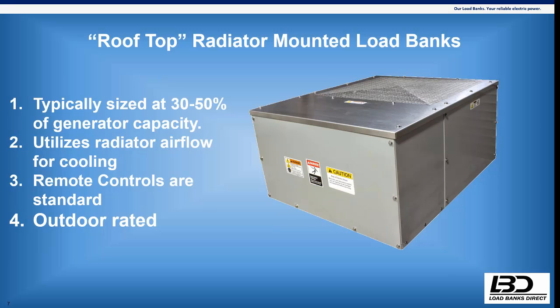On these, remote controls are standard, versus our regular radiator mounted unit where they're local, because these are up on top of the generator and you can't reach up there and operate them. Depending on how it's installed, it can be a very nice, clean installation. You have your controls inside of your enclosure, in your generator control room, wherever you want to mount them, and get the same thing done while also working with a factory enclosure. So it's definitely budget driven. Very, very frequently, I see it's budget driven. That is how we end up with these.